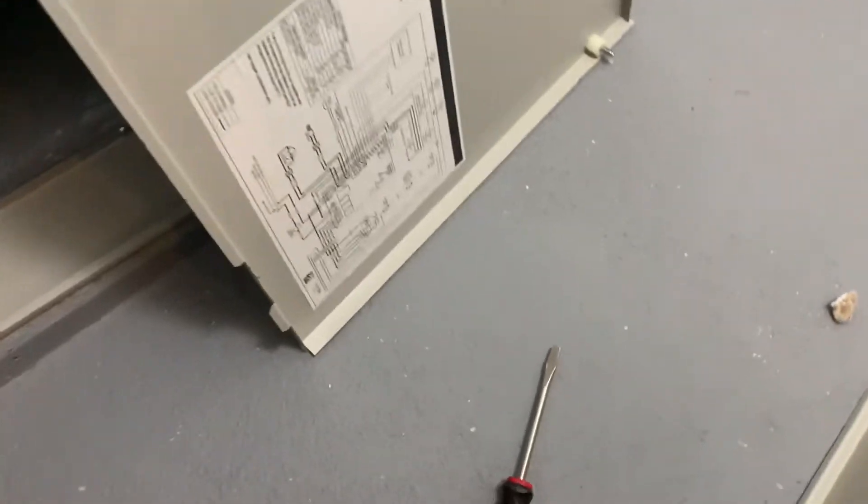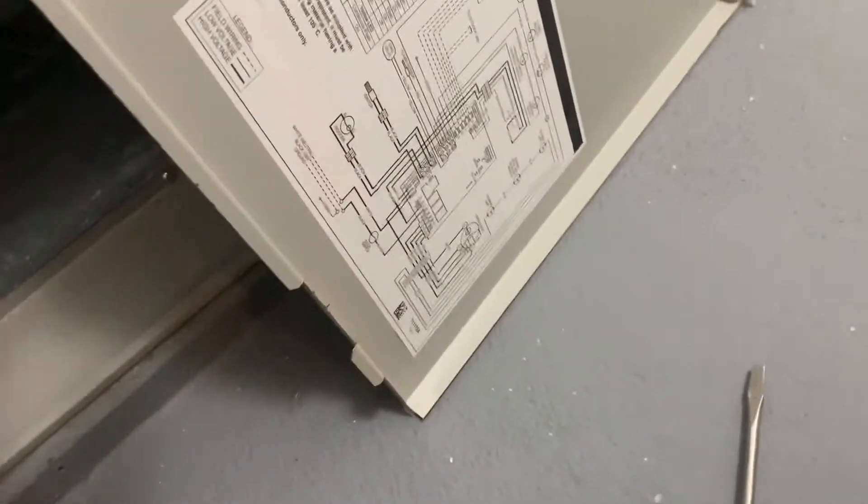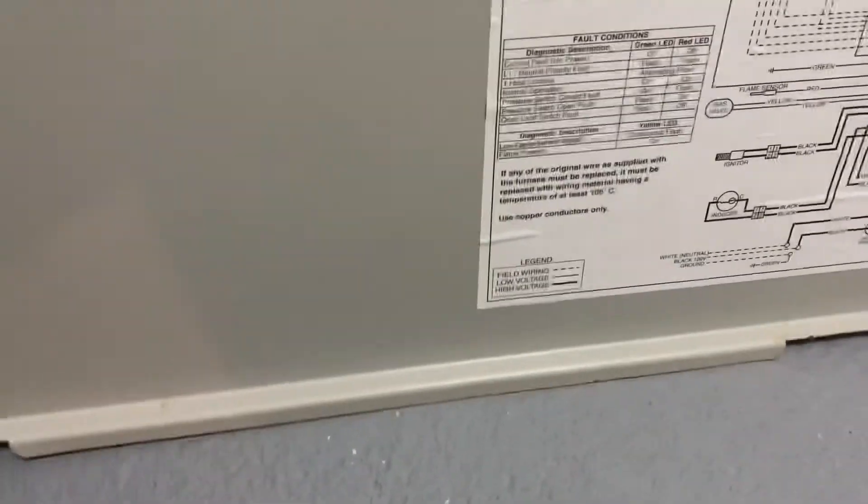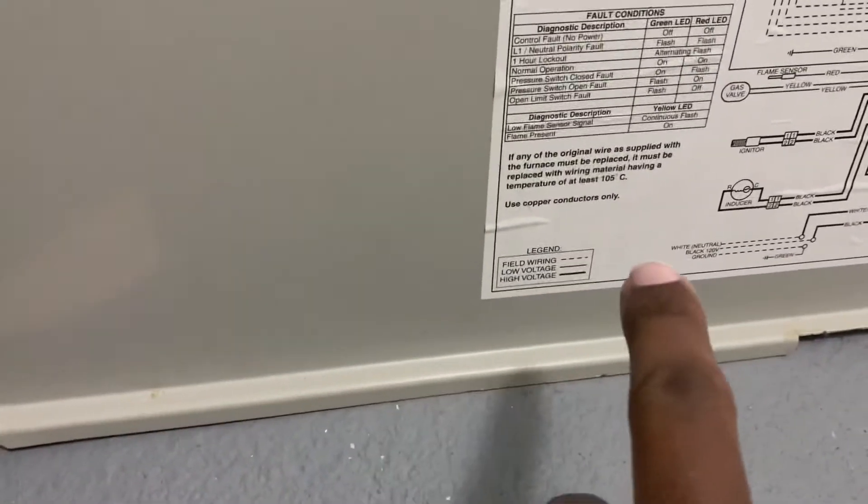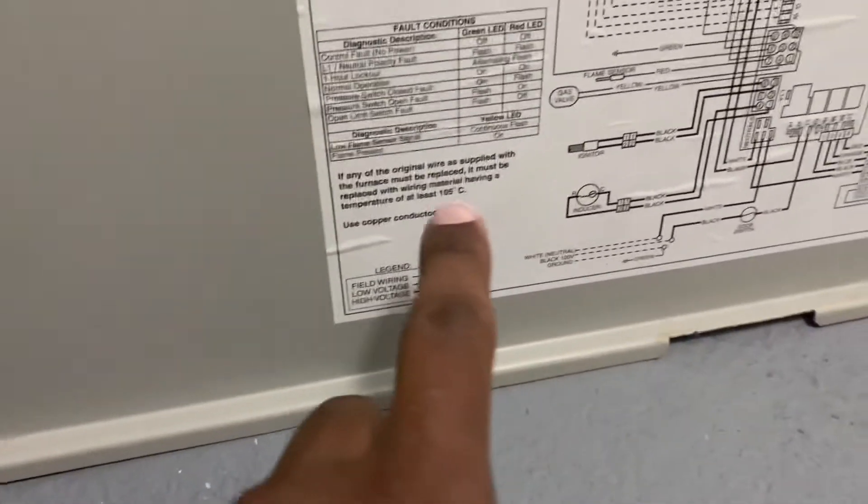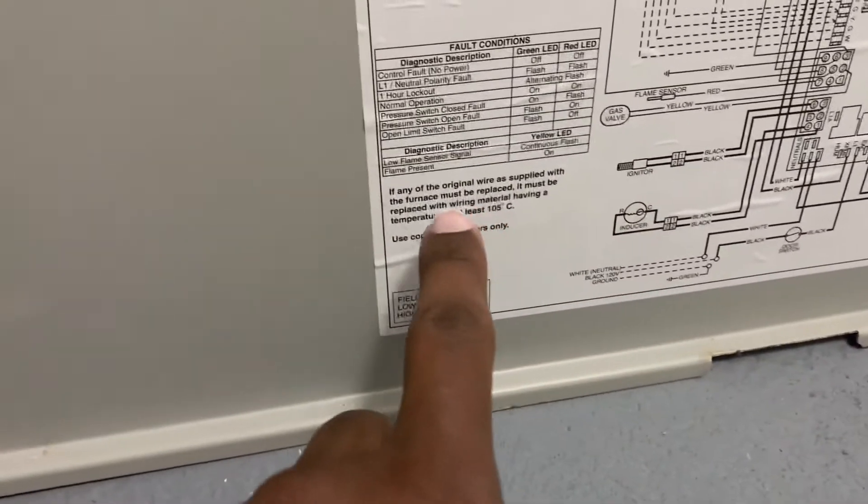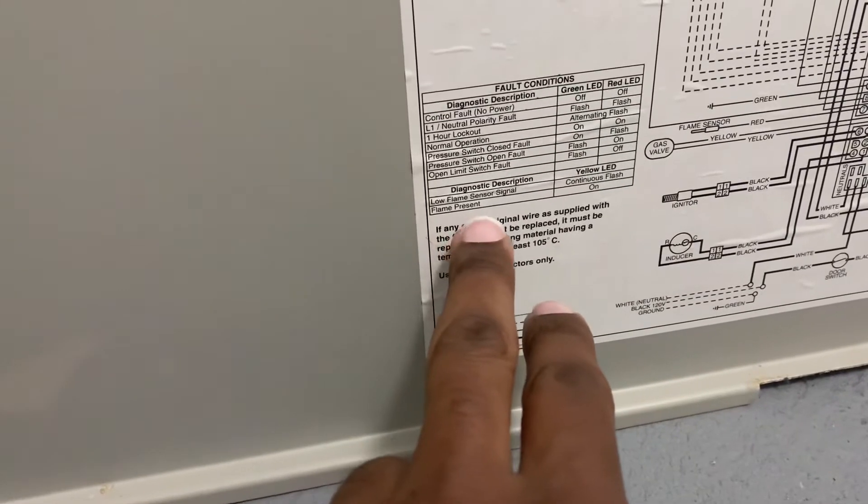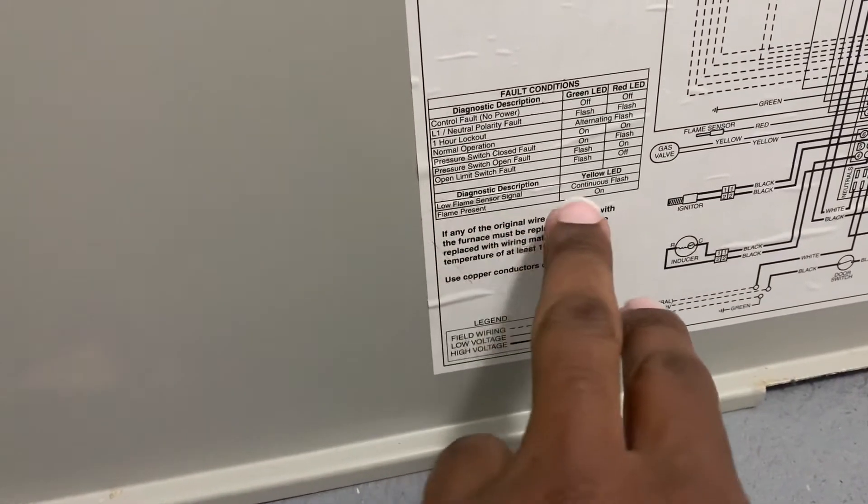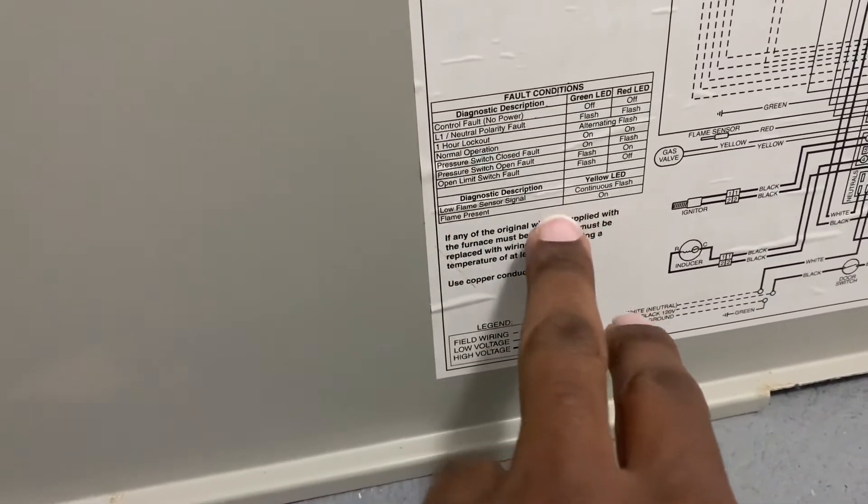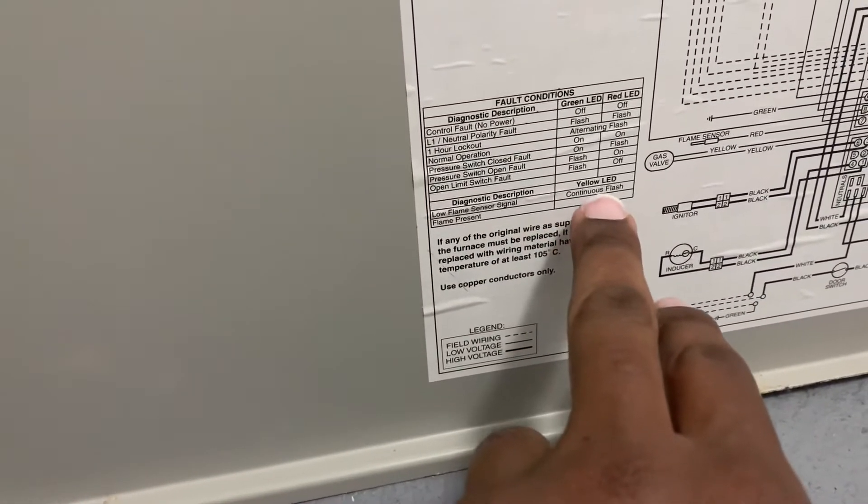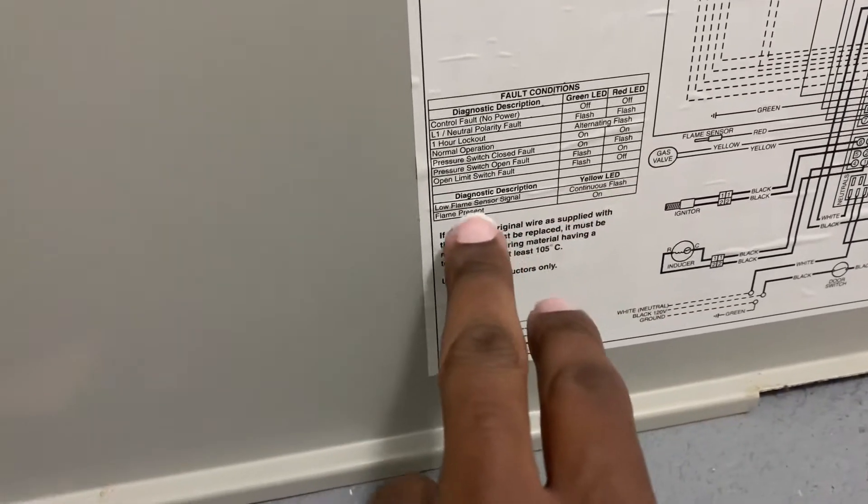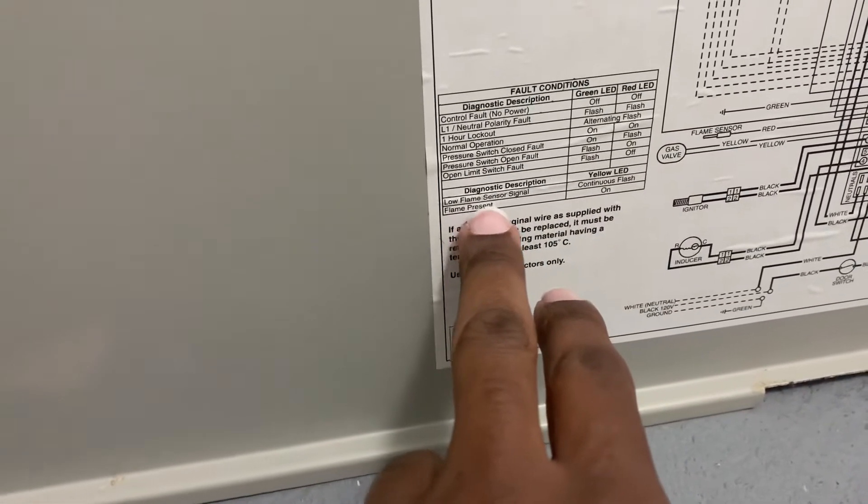I know it's the flame sensor because of the diagnostic description. I have a yellow light continuously flashing, so that's the low flame sensor signal.